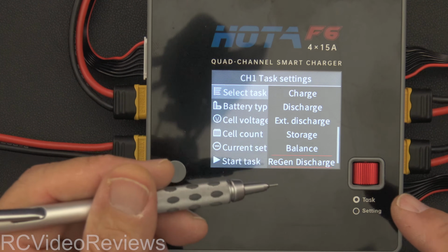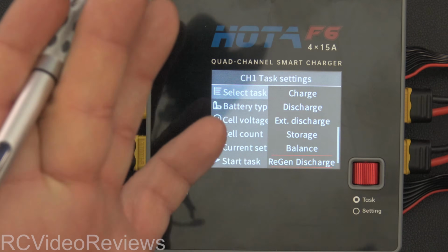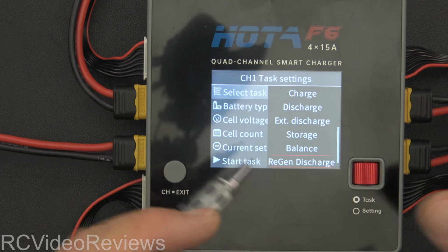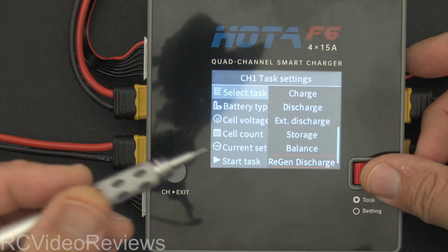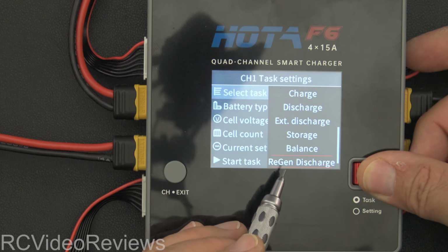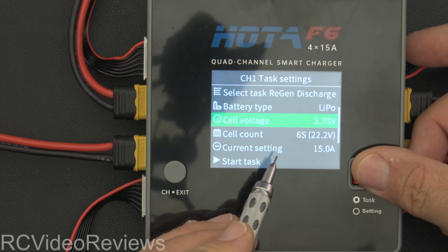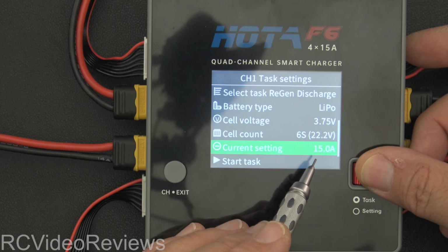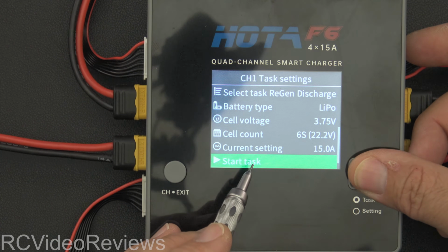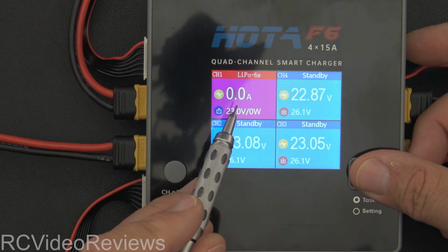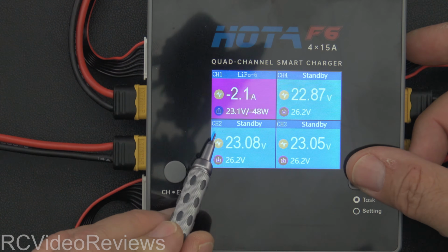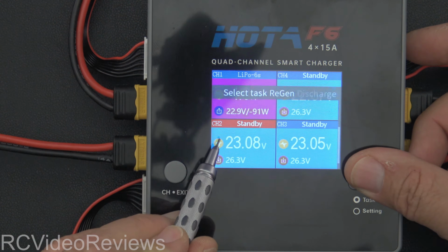And also notice it's got this balance function. I like that one a lot. If you're done charging for the day, you can hook a battery up and just say, hey, balance this for me. But I'm going to set this on regen discharge, and notice the current. I've got it set at 15 amps and we have the cell voltage set at 3.75. So I'm going to hit start, and now we can see channel 1 is going through and that'll climb.